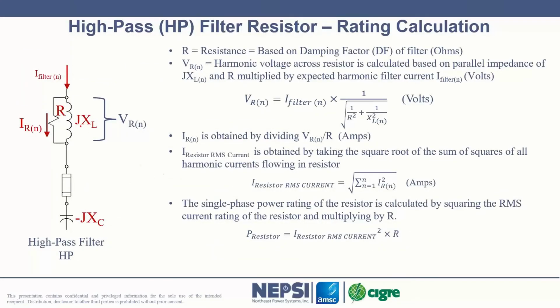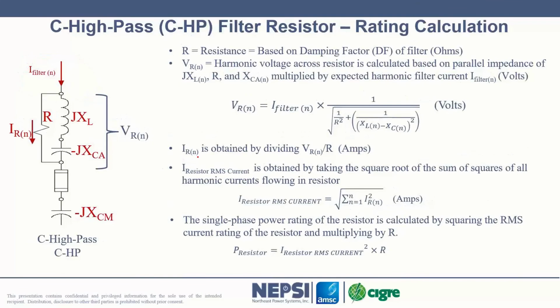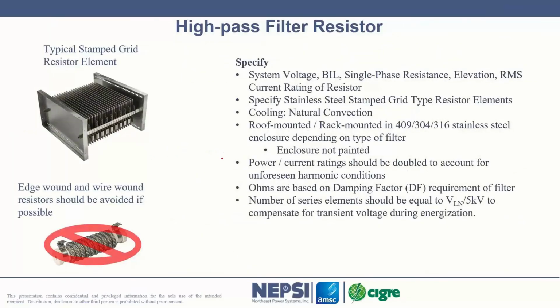So the calculation of the losses essentially is to determine the voltage across the resistor through calculations, and then take V squared over R to come up with the watts per phase. And again, here you want to be conservative. Why? Because you may have more harmonic current flow than what you anticipate. The other reason to be conservative, which I will show you in a minute, is that it allows you some flexibility in the damping factor in your filter design. So for the C-high pass filter, the formulas just get a bit more complicated, but again, they're there, and they're all in that spreadsheet tool.